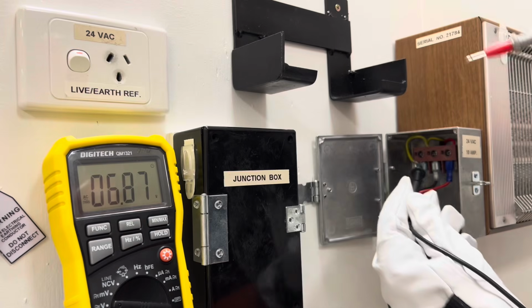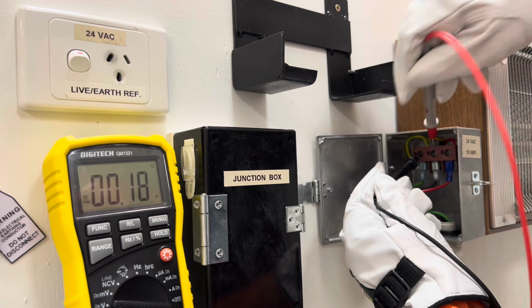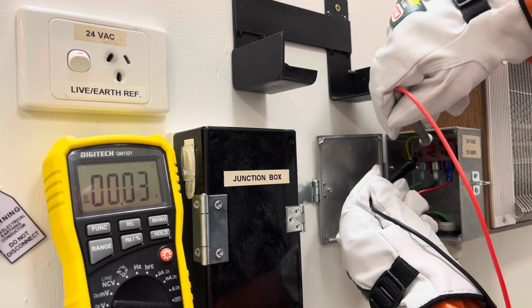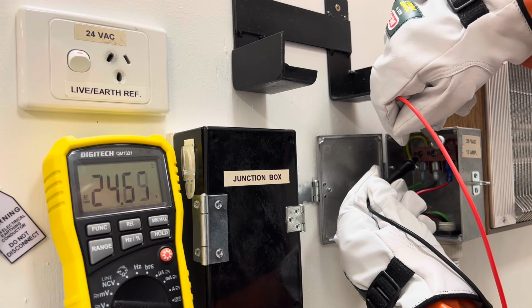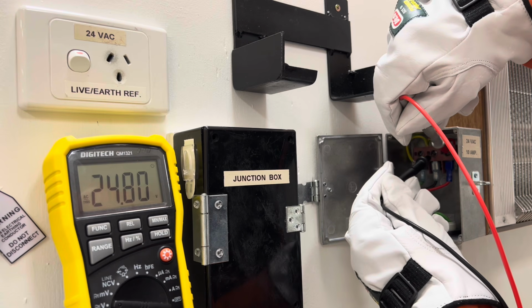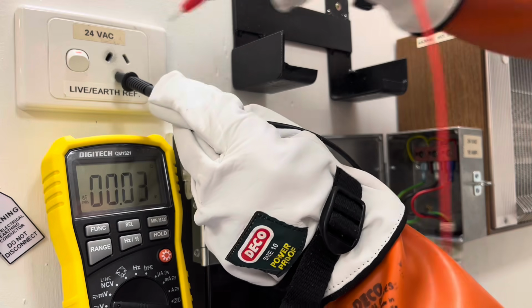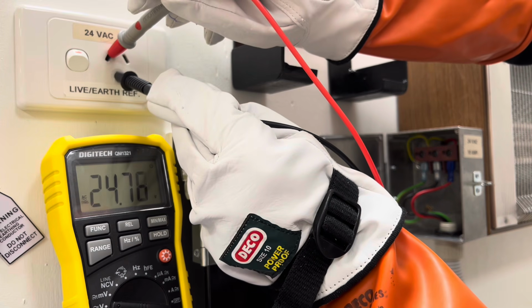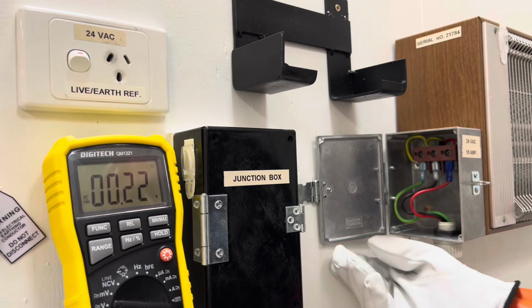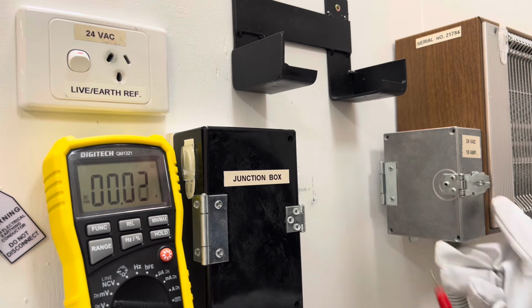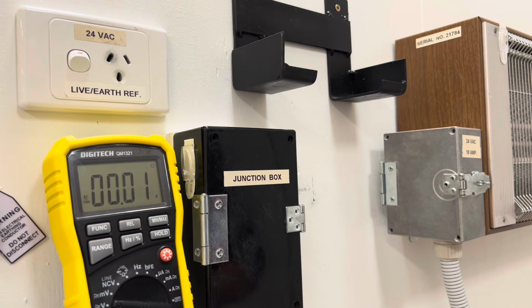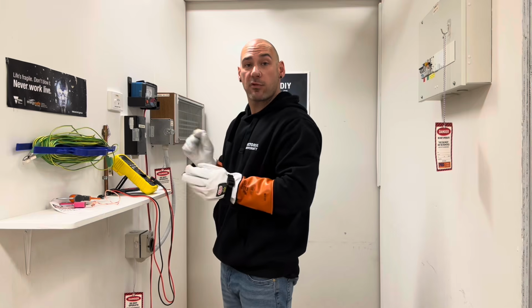And I'd like to do just one last test on the conductors. Earth to neutral, 0 volts. Earth to active, 24 volts. And neutral to active, 24 volts. We test our tester to make sure it's working, and we have 24 volts. That's awesome. Pretty happy with that. Okay, at this point we can start removing our tags.